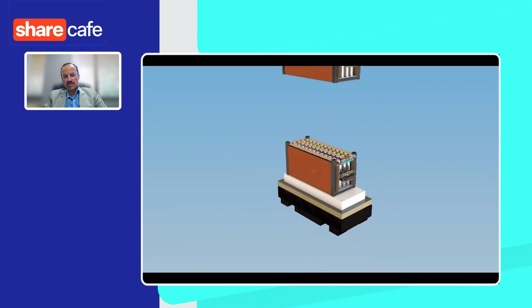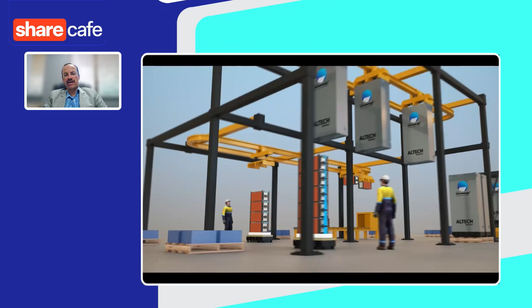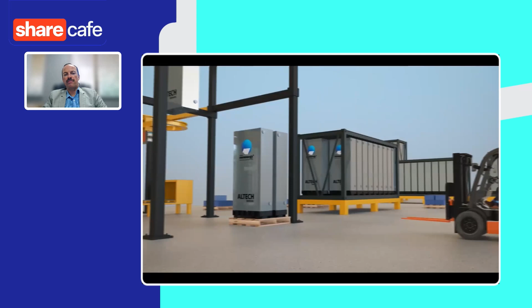What we're seeing in this vision is a 60 kilowatt hour battery pack. This battery pack contains 240 of those 250 watt cells, 48 cells in each rack, 5 racks stacked high to create 60 kilowatt hours of battery capacity in a completely insulated pack. Altech then takes 18 of those 60 kilowatt hour battery packs and puts them into a standard 20-foot sea container. That creates 1 megawatt hour of power, or for people doing the math, it's just over 1 megawatt. 18 times 60 is 1.08, so it's just over 1 megawatt hour of power.